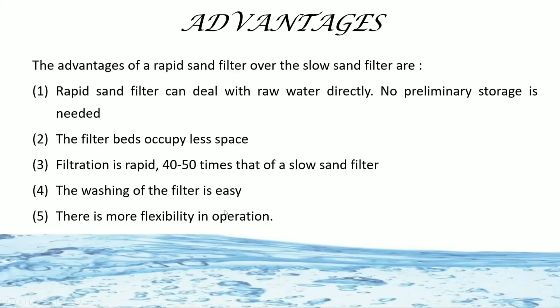So what are the advantages of rapid sand filter? Rapid sand filter can deal with raw water directly. There is no necessity of storage, which is required in slow sand filter. The filter beds occupy less space. Filtration is rapid, almost 40 to 50 times that of slow sand filter. The washing of the filter is easy.